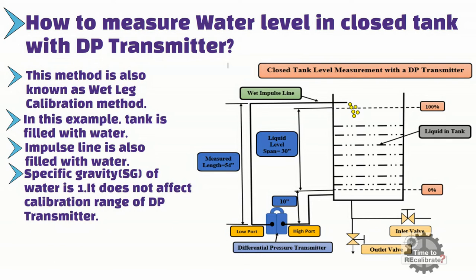However, if the impulse line or tank is filled with another fluid, then we need to multiply the specific gravity of the process fluid with the height of the liquid to calculate the calibration range. As you can see from the picture, zero percent is the minimum level of liquid in the tank, and 100% is the maximum level. Transmitter position does affect level measurement in the wet leg calibration method. So if your transmitter is installed below the zero percent baseline, you need to measure the distance between the transmitter and the zero percent baseline.